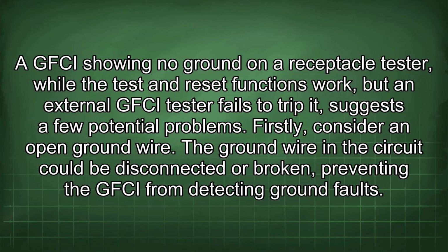A GFCI showing no ground on a receptacle tester, while the test and reset functions work, but an external GFCI tester fails to trip it, suggests a few potential problems. Firstly, consider an open ground wire. The ground wire in the circuit could be disconnected or broken, preventing the GFCI from detecting ground faults.